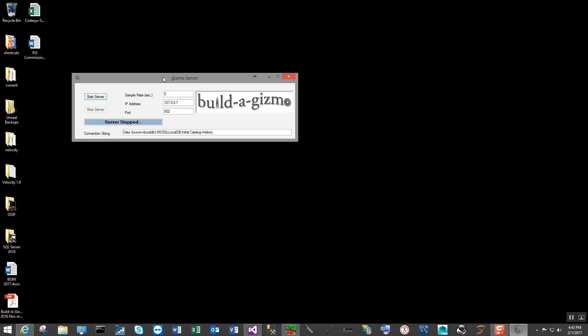This is the basic UI, and I can change the sample rates, anything I like. It does go down to one sample per second, which means one full row of data of all 96 registers with a timestamp will go to the SQL Server every second if necessary. I tend to go up to 5 to 10 seconds on big factory jobs so that I can collect the data robustly and report on it through the SQL Server, so I don't have to build any fancy Modbus gateways, which are difficult — especially in the cloud — to get my data directly from the devices.